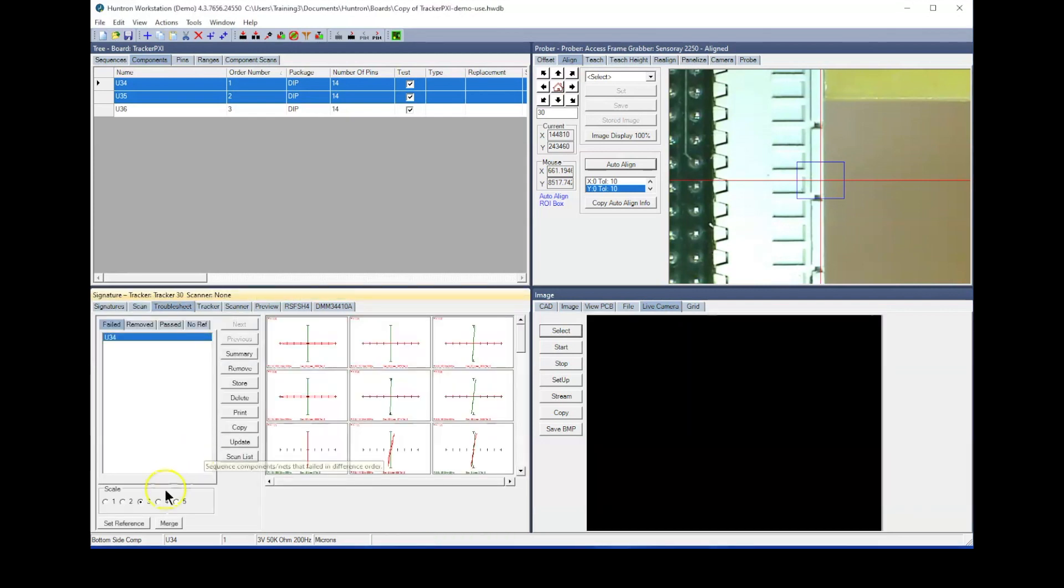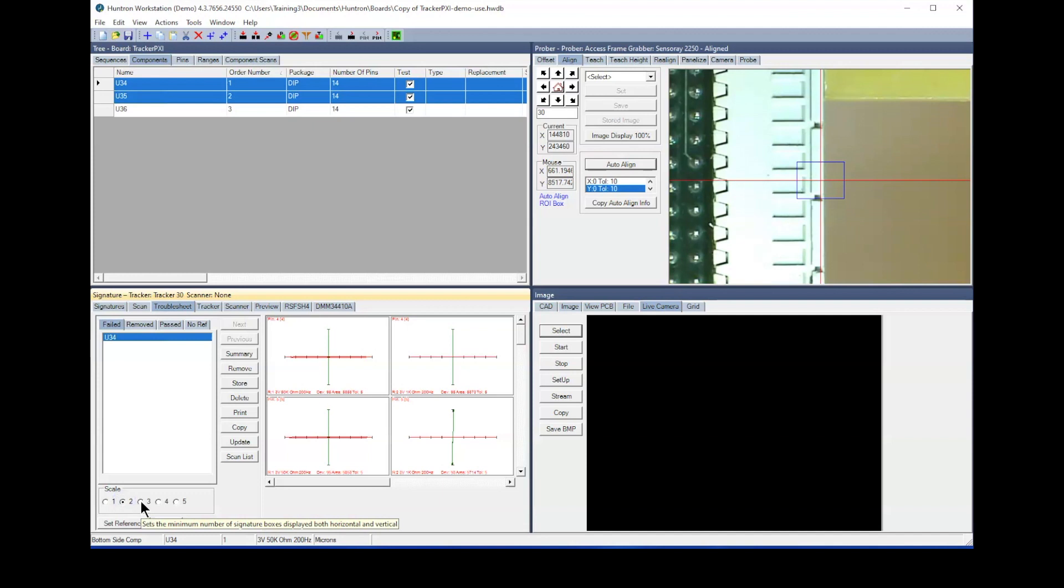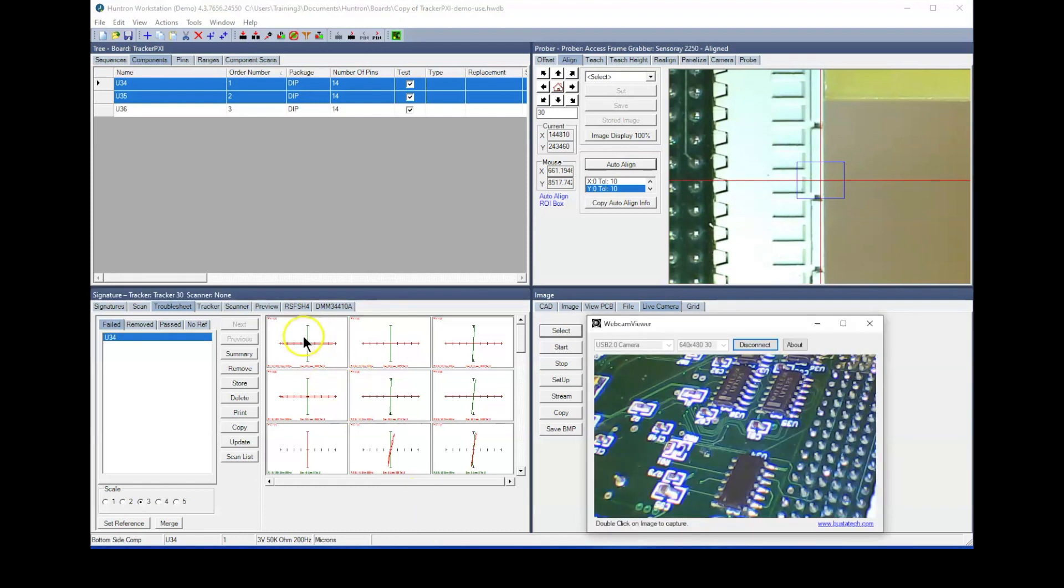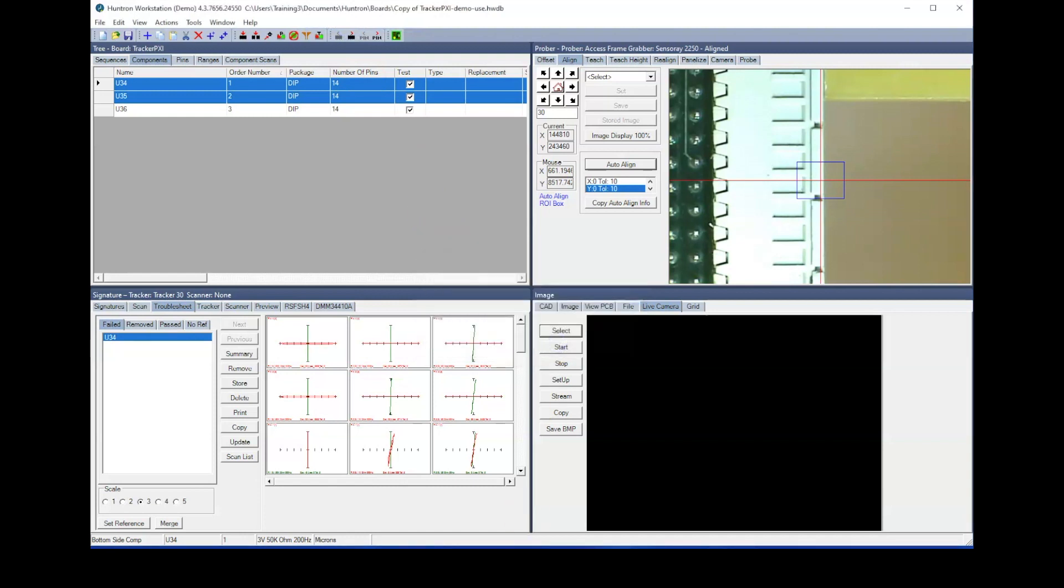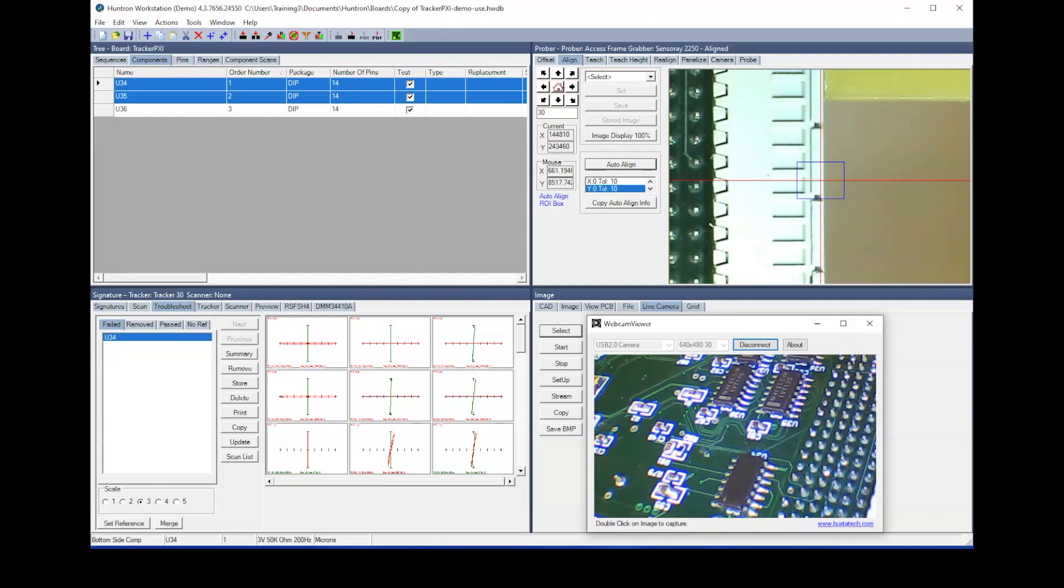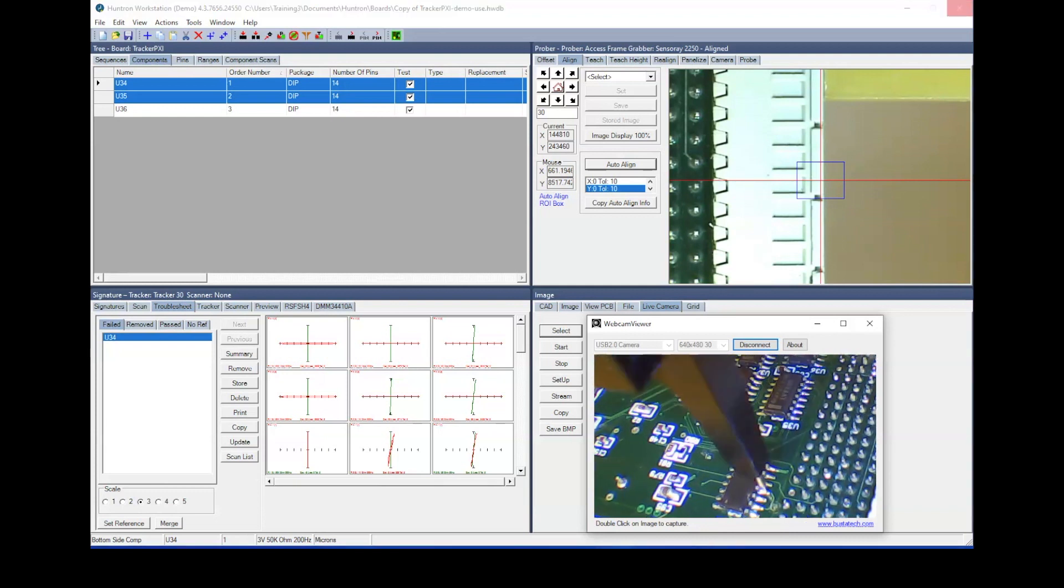Another option in the signature box right-click menu is Reprobe Opens. Before using this selection, select the signature scale to display as many pins as possible. Select Reprobe Opens and the prober will go to each open pin, rescan the signatures, and replace the original ones.